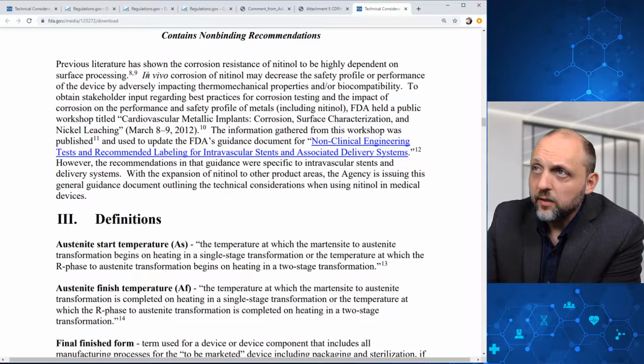Here we see some details about the previous literature and a couple references. In vivo corrosion of nitinol may decrease the safety profile or performance of the device by adversely impacting thermomechanical properties and/or biocompatibility. To obtain stakeholder input regarding best practices for corrosion testing and the impact of corrosion on the performance and safety profile of metals, FDA held a workshop in 2012, and information gathered from that workshop was used to update FDA's guidance document here on non-clinical engineering tests and recommended labeling for intravascular stents and associated delivery systems. And here they call out that the recommendations of that guidance were specific to intravascular stents and their delivery systems.